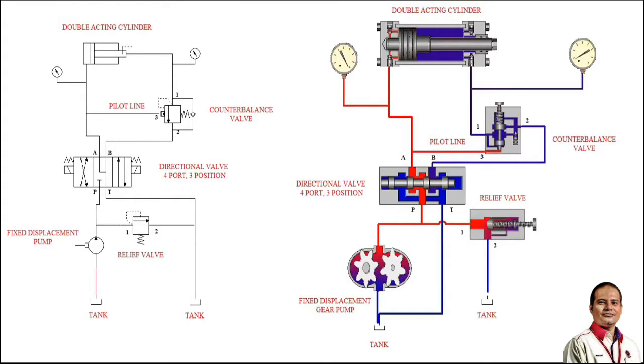So now I will advance it again, and you see at this point between those last two frames the relief valve closed off. So now the pressure here, the fluid takes the path of least resistance, which in this case is into the piston end of the cylinder. So at this point, what do we want to look at? Well, for one, the red is indicative of the higher pressure, blue is indicative of the lower pressure, and there are varying colors in between that represent the intermediate pressures.